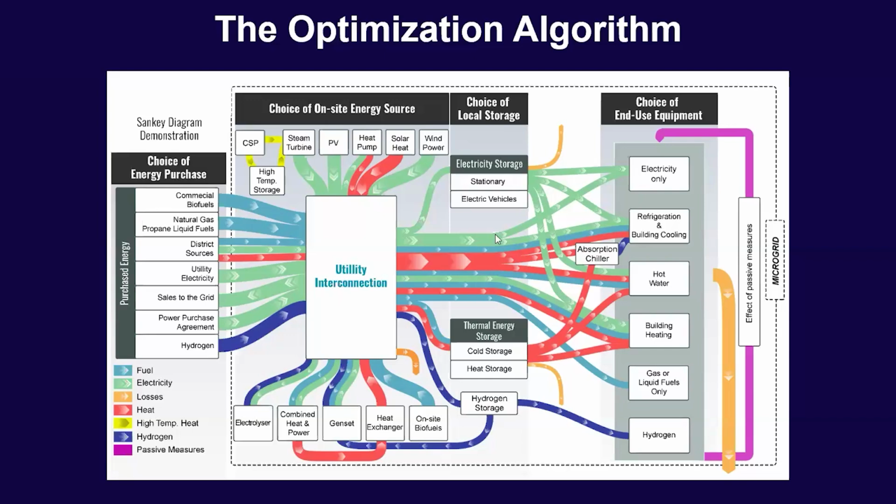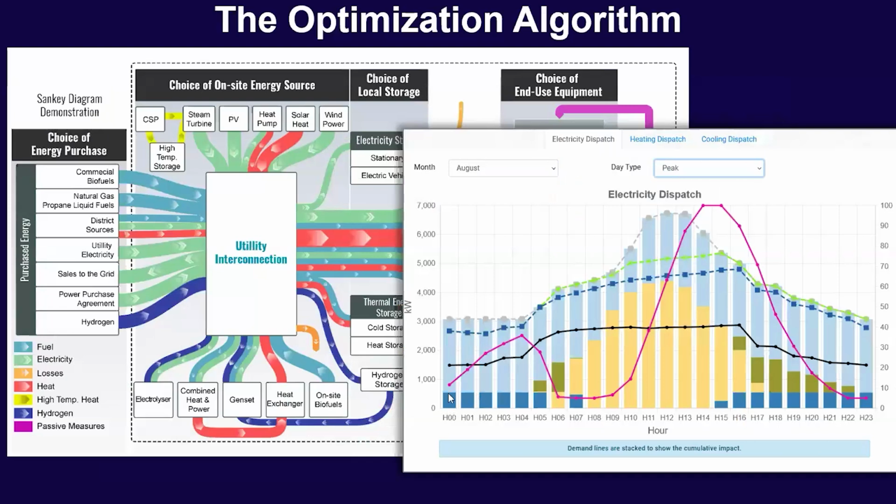And this is what I'm saying here. When we design a system, it's not only giving you the capacity, but also, for every month and period, how you should run the technology. Here in black we have the electricity demand that was provided through the database, through an API, whatever it is. Then in darker blue bars, we have the utility demand. And as you can see, it's pretty flat. It's going away during the day because of PV, but it's really flat because it does demand charge management.